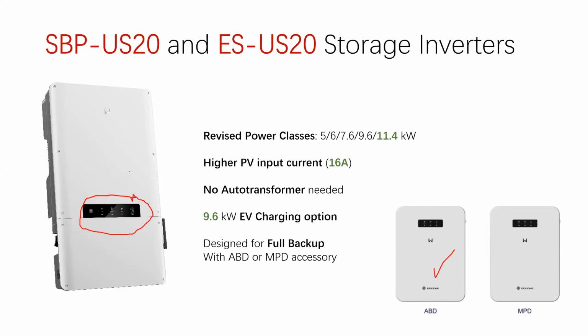If you want to put multiple of these inverters at a site, you will need something to manage the fact that they're all competing to form the AC waveform when the grid goes out. You need a master or multiple parallel device, and that's what this is if you want to connect more than one inverter at a site to the same load panel.